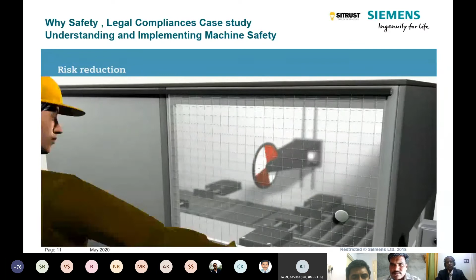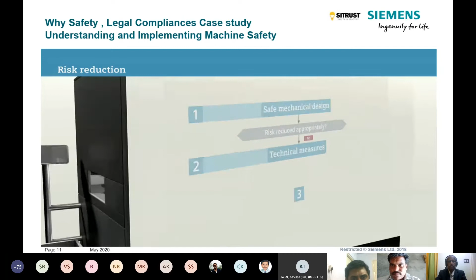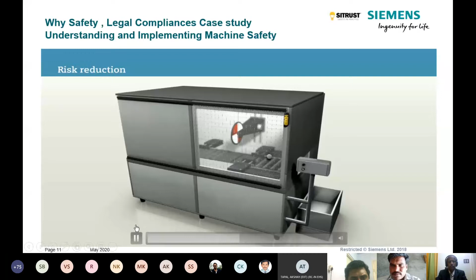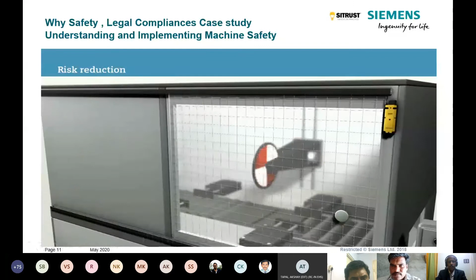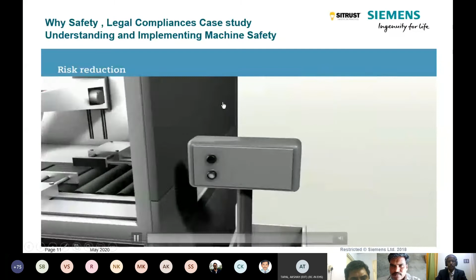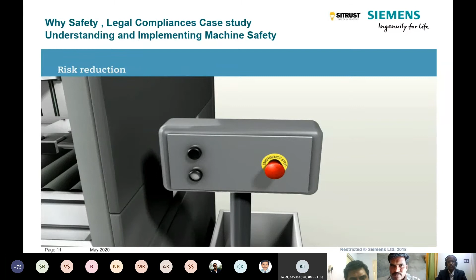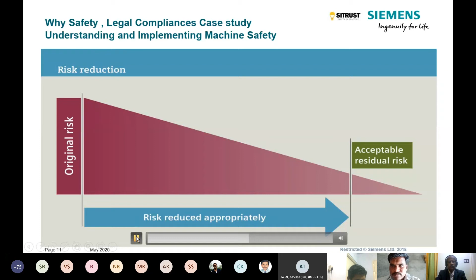If the construction doesn't lead to an acceptable residual risk, you must, according to the three-level method, define additional technical measures in the team. For our machine, the installation of a safety position switch for door monitoring would be such a technical measure. In conjunction with a safe evaluation unit and 2 actuators, opening the sliding door then leads to the machine coming to a standstill. With an additional emergency stop commanding device, the operator can also switch off the machine in the event of danger. The assessment by the team shows that these 2 safety functions reduce the original risk to an acceptable residual risk. According to the 3-level method, no further measures are necessary in this case.